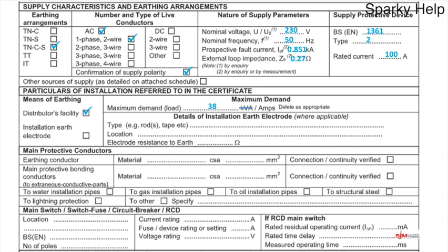So if you do come across smart meters, they record lots of information. Go back to the actual meter itself, not the remote box, because I'm not sure they all do it on that. On the meter itself, there'll be a button you can press to cycle through, and you can see information like volts, amps, power factor even, but also kVA, amps, and maximum demand available in there. So you can tell, and it would be accurate. Obviously, the longer it's been in, the more accurate it would be. So we put something in for maximum demand. It's an assessment. It's your assessment in this case.